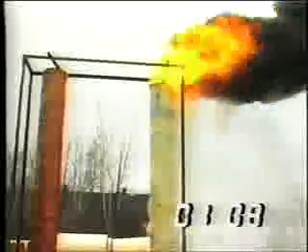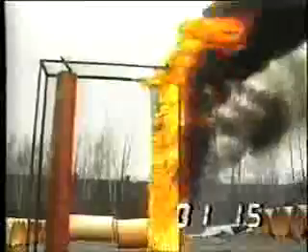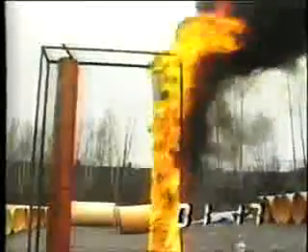The charring effect on the 10-foot length of duct is noticeable, with flame visible at the top of the duct. Even when the heptane has burnt itself out, the polyester duct continues to burn very strongly, and acrid black smoke is generated, although the toxicity of the smoke was not measured in the test. It is, however, known that since the flame retardant additive in the resin contains antimony and halides, the smoke generated contains these compounds. The polyester resins are petroleum-based products, unlike the phenolic resins, which are water-based.